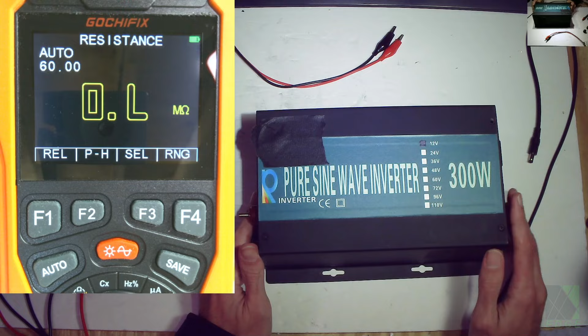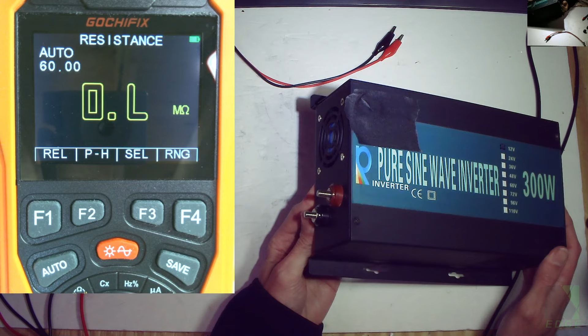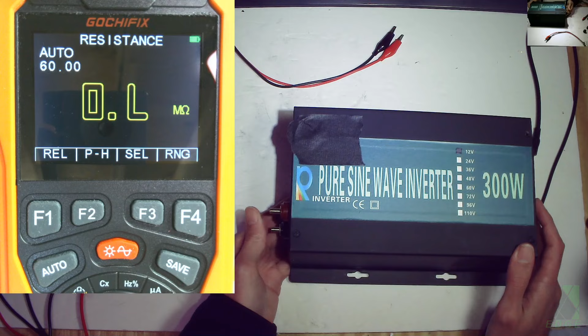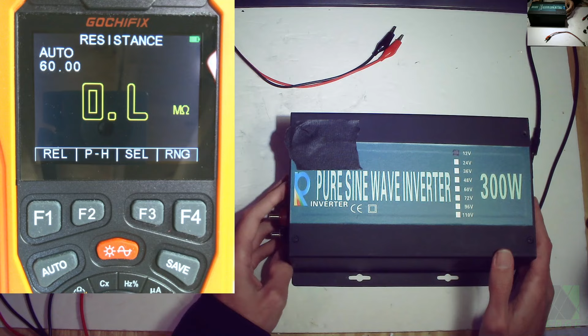Okay, to summarize, if you're going to check the input stage of the inverter: inverters have an input stage, that's where your battery connects, and they have an output stage, and that's where you plug in your AC appliances, high voltage. Let's summarize the input stage. If I check the input of a DC to AC inverter with a multimeter, and it says open circuit, you're going to have to open the inverter to look inside. If the fuses are not external, more than likely you're going to have to open the inverter. If you replace the fuses because of an open circuit condition, very, very likely what's going to happen when you power the inverter up is it's just going to blow the fuses again.